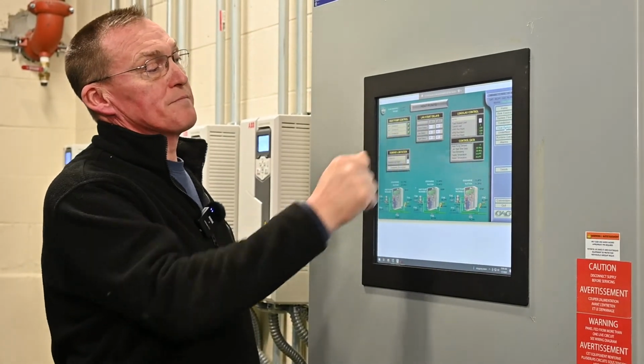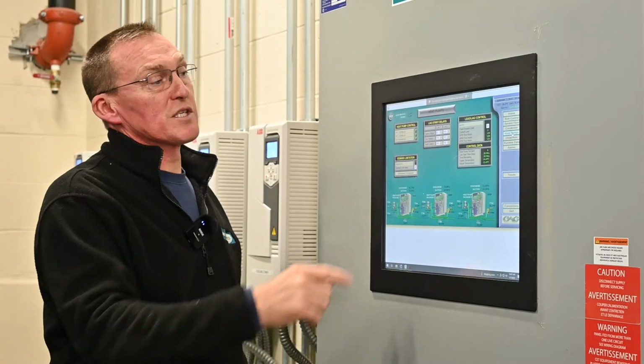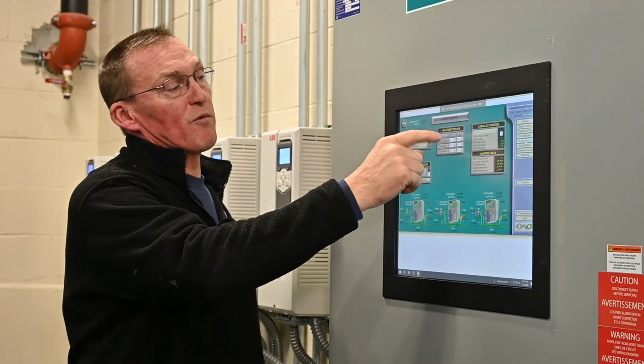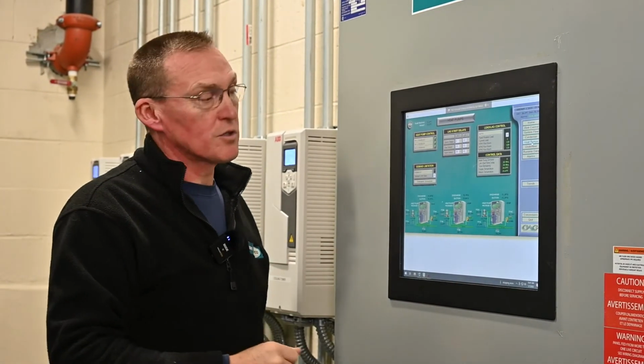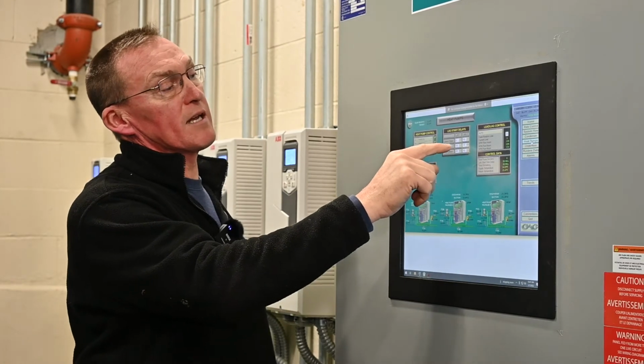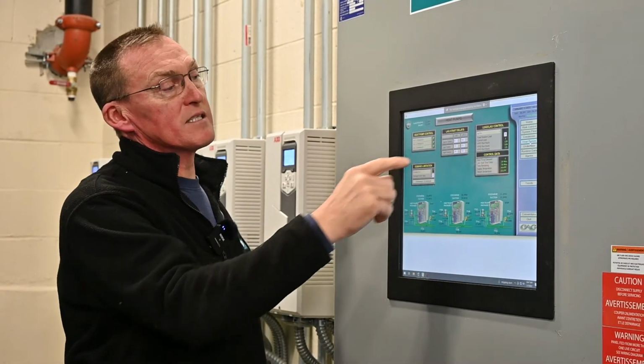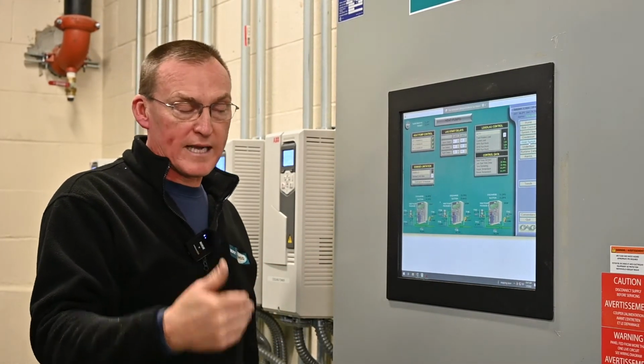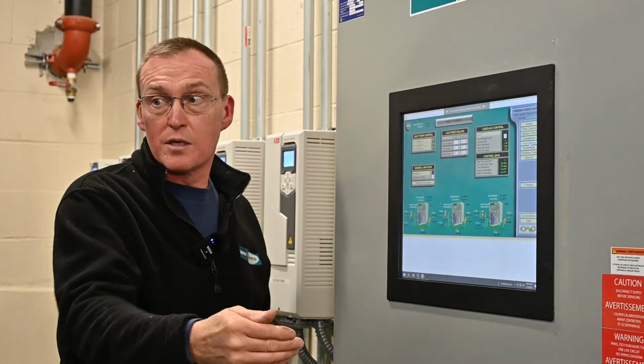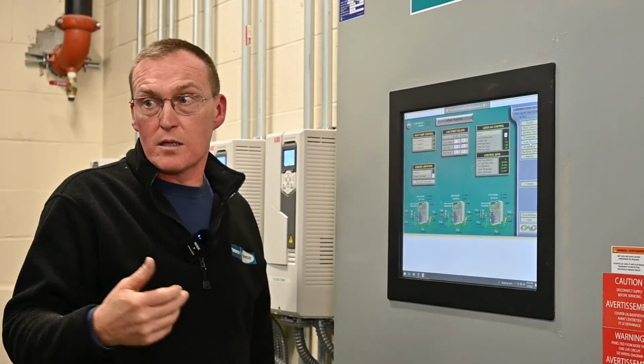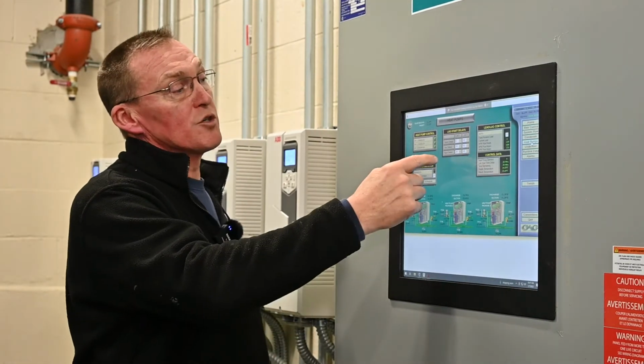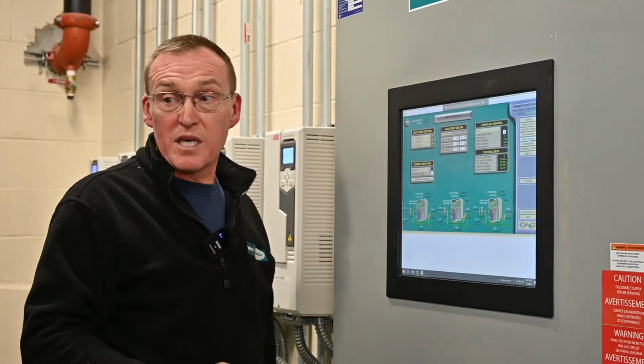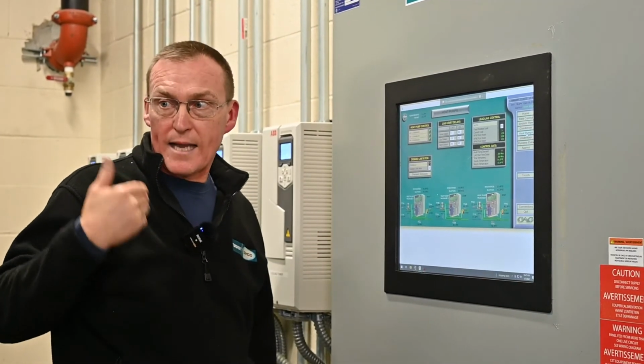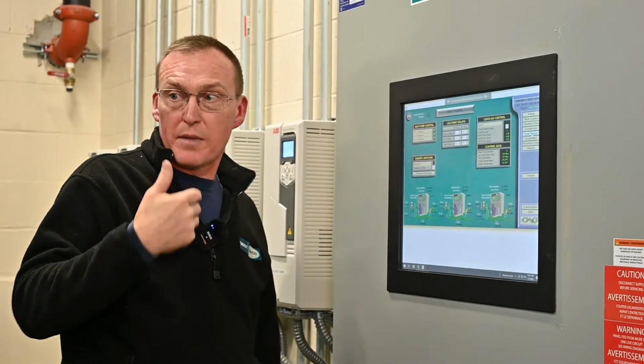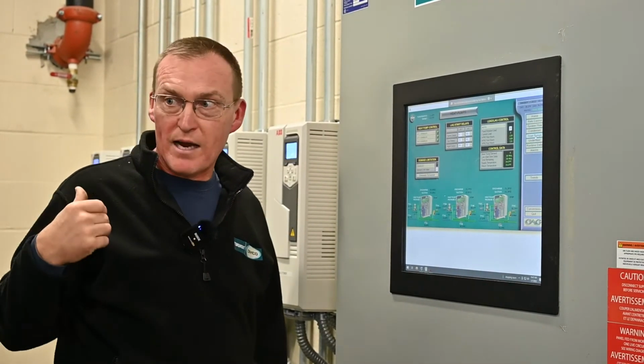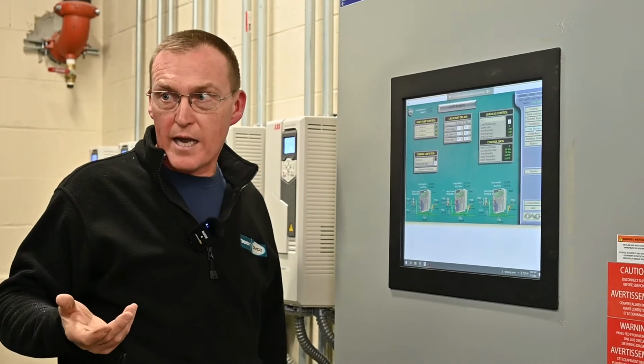Lag start delays. This is how long it takes before each compressor starts. So once you start the first one, if you're running in day right now, after the first one starts, it will then start counting, in this case, 15 minutes. You can increase these times based on the load that you have. If you go to night, you may decide that you want to bump that up to 60 minutes and wait for that last machine. Let the other 2 run. Maybe they'll pull the load, and then you'll never have to have that third one start. Energy savings.